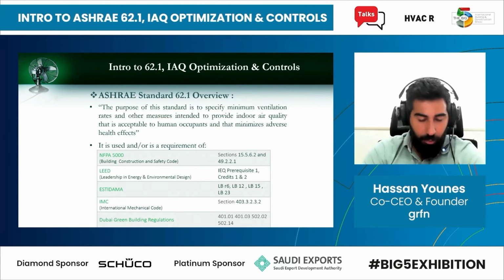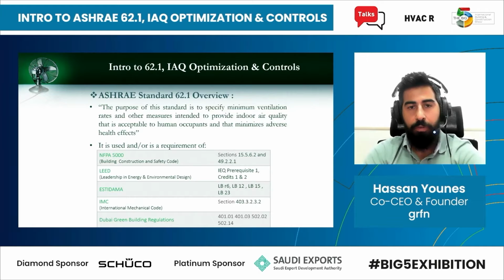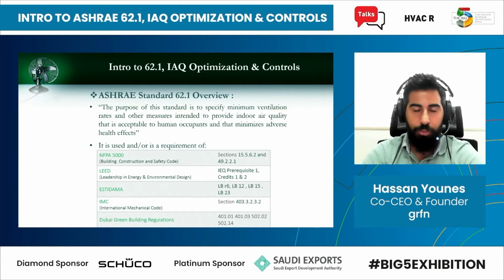So what is standard 62.1? The purpose of the standard is to specify minimum ventilation rates and other measures intended to provide indoor air quality that is acceptable to human occupants and that minimizes adverse health effects. That's basically the standard's purpose. If you look at the document, that is exactly what it says there.